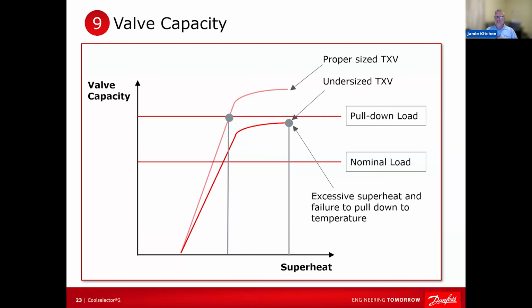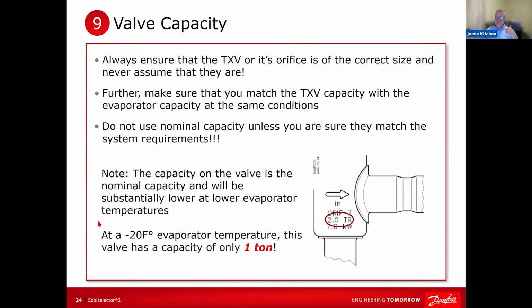So these are the things that make them stand out, right? So when are you going to see an undersized TXV? Unless it's drastically undersized, you're going to see it generally when you put a load on the system. Or you size it for a cooler and you use it in a freezer. So remember, nominal capacity is good for replacing like for like. So if you have a nominal 1-ton valve and you replace it with a nominal 1-ton valve, as long as the first one was sized correctly, you're good. But if you have a 1-ton unit cooler evaporator in an ice cream freezer at -20, that nominal 1-ton valve is going to give you half a ton. Yeah. And if you need 1 ton, you're going to be grossly undersized.